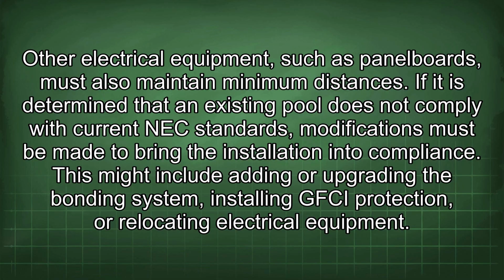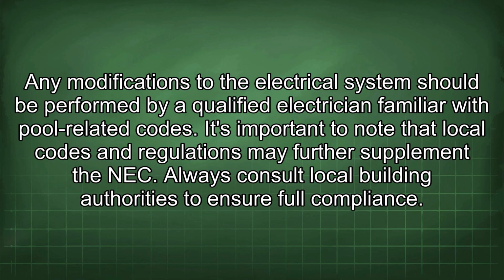If it is determined that an existing pool does not comply with current NEC standards, modifications must be made to bring the installation into compliance. This might include adding or upgrading the bonding system, installing GFCI protection, or relocating electrical equipment. Any modifications to the electrical system should be performed by a qualified electrician familiar with pool-related codes. It's important to note that local codes and regulations may further supplement the NEC. Always consult local building authorities to ensure full compliance.